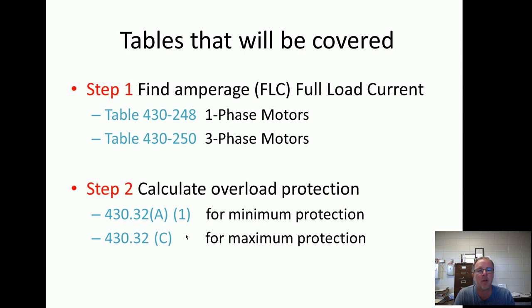The tables we'll be covering today: for step one, Table 430-248 for single-phase motors, and Table 430-250 for three-phase motors. That's step one. Step two, we're going to calculate the minimum overload protection and the maximum overload protection — 430-32A1 and 32C. So there are four articles we're going to be looking at.